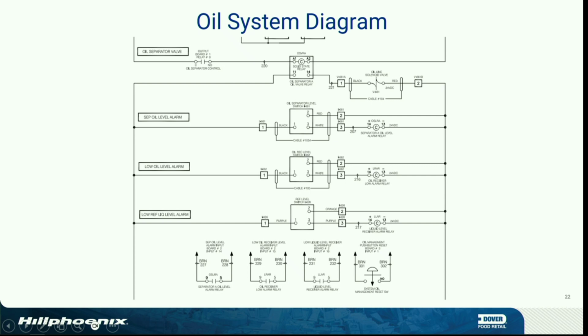And the reason we pulse is we don't want to just turn the oil solenoid on and start dumping hot vapor and liquid into our reservoir, right? Does anybody know where the reservoir vents? Your vessel. To our vessel. So our reservoir is the exact same pressure as our vessel. And that's an important thing we'll come to in a little bit. If we just continue to dump that hot gas, we're putting it in the reservoir, it's going to end up in the vessel. Then where's it going to go? Come on, Brian. We talked about this.